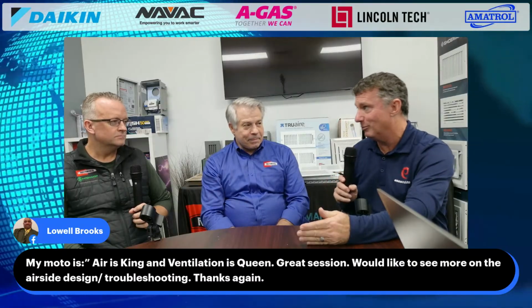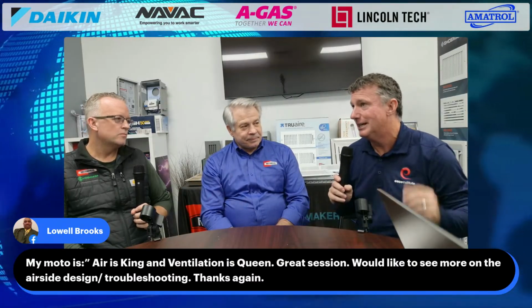Yeah, and it is. On the air side, troubleshooting is becoming so important in our industry, and a lot of it does have to do with our high efficiency equipment. These ECM motors - when we looked at PSC motors, they trended the same all the time, their permanent split capacitor had a very standard curve to it. When we went to ECM, we went to two different styles: a constant torque and a constant airflow. Both of them respond differently to external static pressure. And one of the things you hear from the industry that is so completely wrong is that ECMs overcome static pressure - nothing overcomes static pressure.